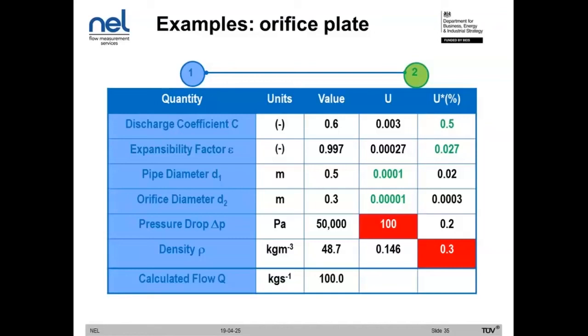For the pressure drop and the density, there's a bit more work involved because there's various parameters that feed into each of those. With the pressure drop, for example, we have the performance of the pressure transmitters, but also the calibration which they were subject to, and the uncertainty of the standard which they were calibrated against. But then we also have the performance of the device under real conditions, like how repeatable is it, and what is the standard deviation and the standard uncertainty. With the density, if this is a gas like nitrogen, for example, we can actually work out the density using an appropriate equation of state. That equation of state would have uncertainties attached to it as well. And you would also need temperature and pressure, each of which would have their own component uncertainties. So you could do a deeper uncertainty analysis looking at each of the subcomponents of this table, but this is just a simplified overview.